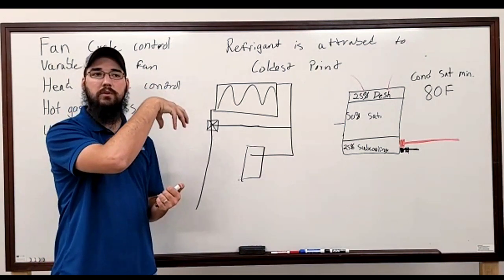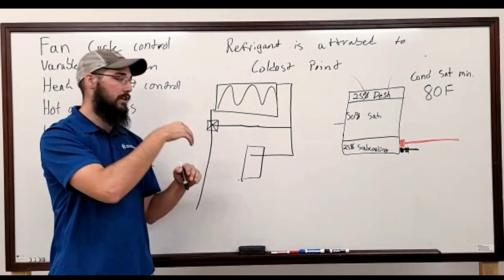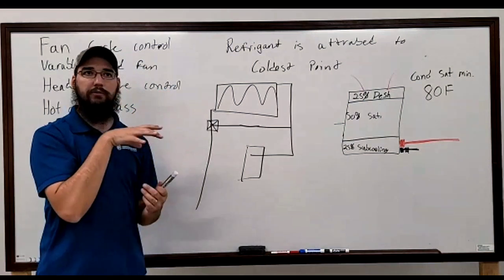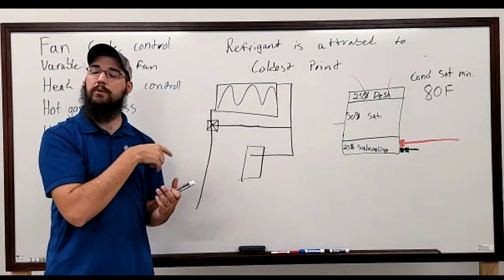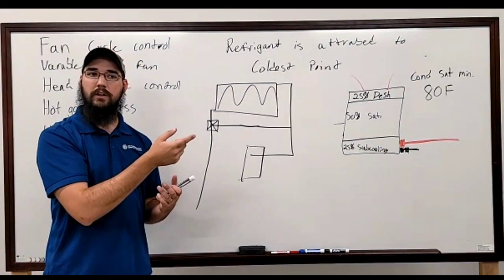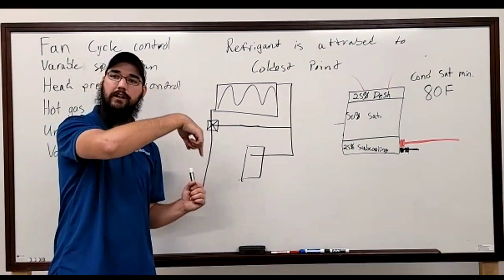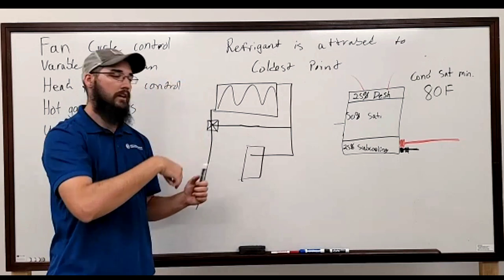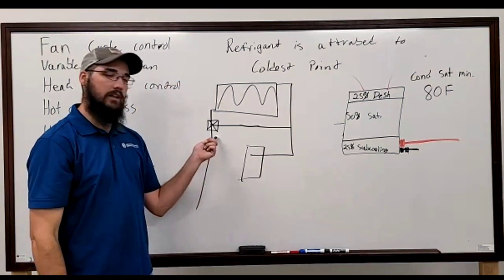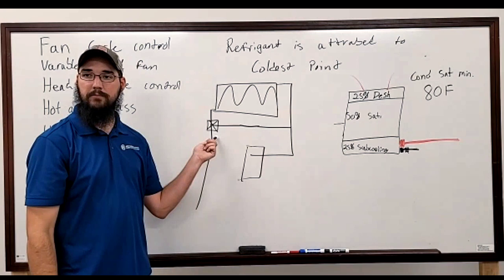Most of the time, in our particular applications, they'll be an adjustable valve with a spring set, and it'll look like a really funky looking TXV, but it won't have a sensing bulb. It'll have a big cone sticking out of the head with a cap you can take off, stick an Allen in, and adjust the spring to set what leaving pressure you're trying to maintain.